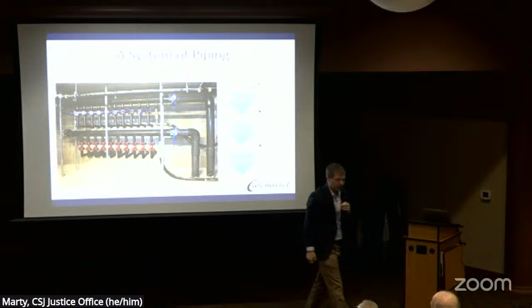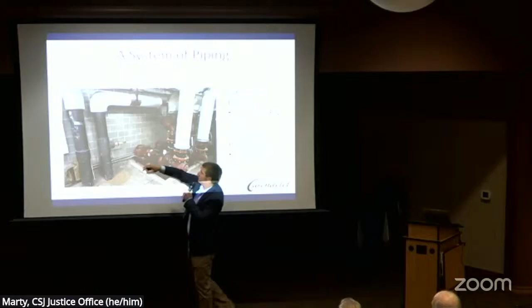So they drop down under the garage floor, and they come across stall 43. And on the other side, this is the parking space on the other side of this wall of stall 43. These black pipes pop back up and they hit a set of pumps. So we've got 2 main sets of pumps. One are the well field pumps, which are these 2 right here. And then next to it is a set of 3 pumps called the core loop.